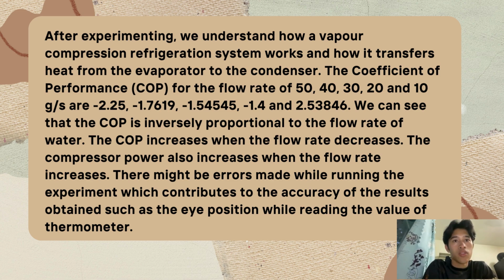2.53846. So from the results that we obtain, we can see that the COP is inversely proportional to the flow rate, which means when the COP increases, the flow rate decreases. The compression power also increases when the flow rate is increased.